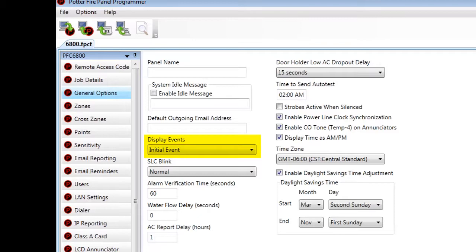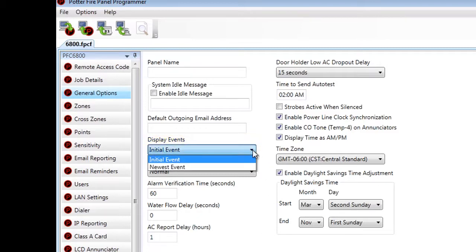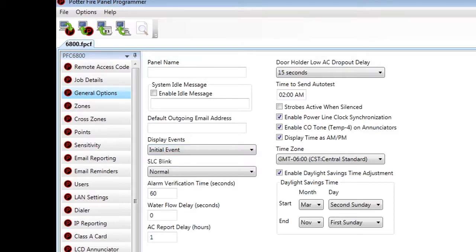Under Default Outgoing Email Address is Display Events. The default is Initial Event; the other option in the dropdown is Newest Event. This refers to the order that active events are displayed on the fire alarm control panel's LCD screen. If you choose Initial Event, when you approach the panel the first event shown will be the very first event that occurred on the system. If you choose Newest Event, you will see the most recent event. In either option you can use the up and down arrows on the keypad to view all events.